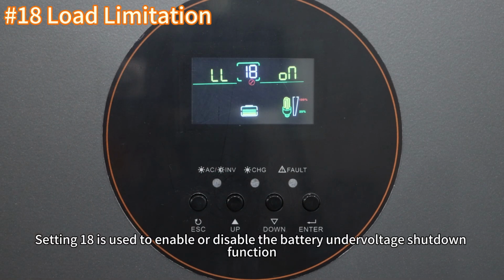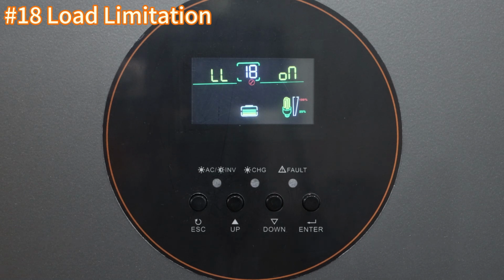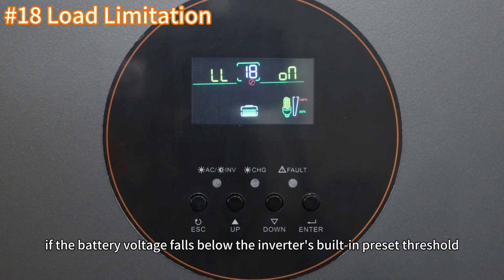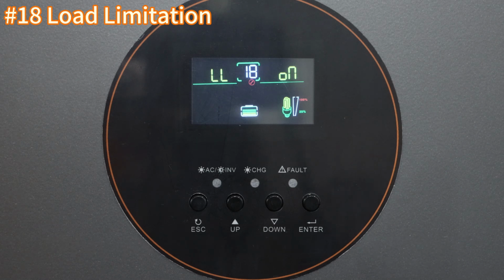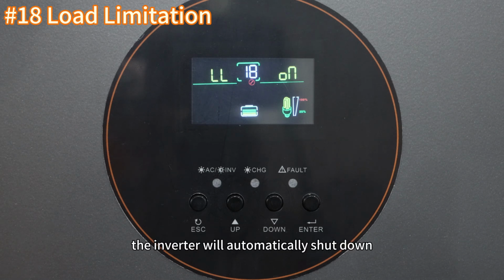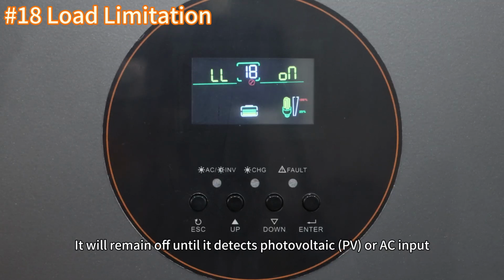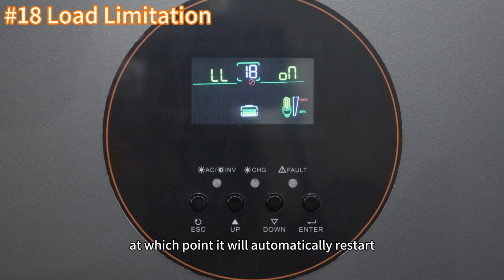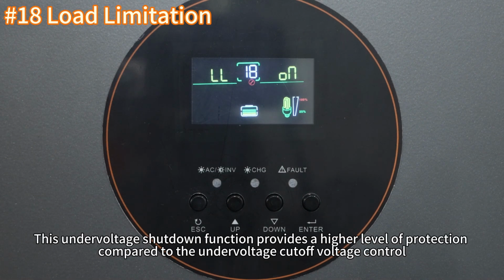Setting 18 is used to enable or disable the battery undervoltage shutdown function. When enabled, if the battery voltage falls below the inverter's built-in preset threshold, the inverter will automatically shut down. It will remain off until it detects the photovoltaic or AC input, at which point it will automatically restart. This undervoltage shutdown function provides a higher level of protection compared to the undervoltage cutoff voltage control.